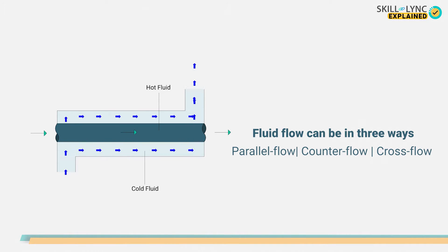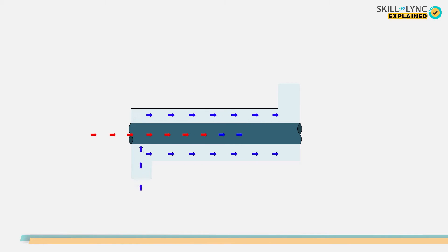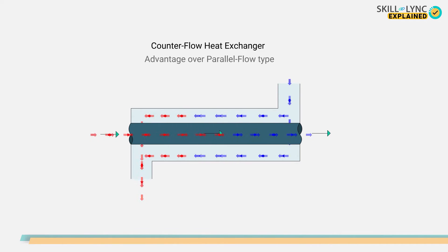Furthermore, the fluid direction can be different in three ways, thus giving rise to three primary classifications of a heat exchanger. A parallel flow heat exchanger has fluids entering from one end, traveling parallel in the same direction, and then exiting from the other end. The other type is a counter flow heat exchanger. In this type, two fluids enter from opposite ends, flow in opposite directions, and finally exit from opposite ends.